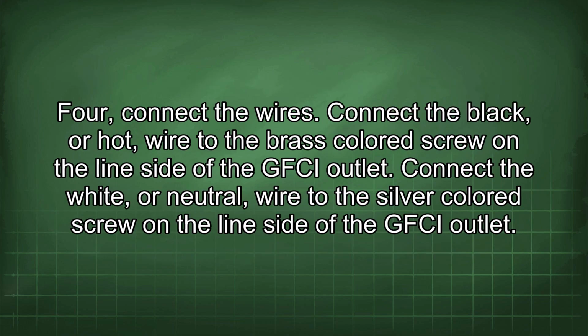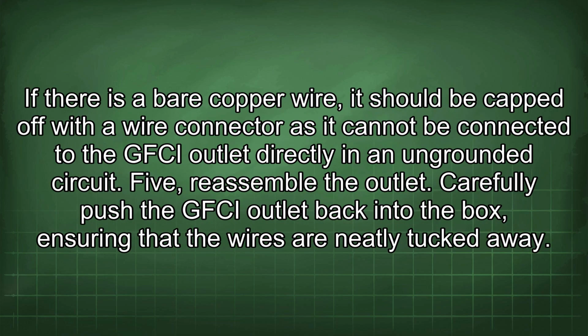4. Connect the wires. Connect the black or hot wire to the brass-colored screw on the line side of the GFCI outlet. Connect the white or neutral wire to the silver-colored screw on the line side of the GFCI outlet. If there is a bare copper wire, it should be capped off with a wire connector, as it cannot be connected to the GFCI outlet directly in an ungrounded circuit.